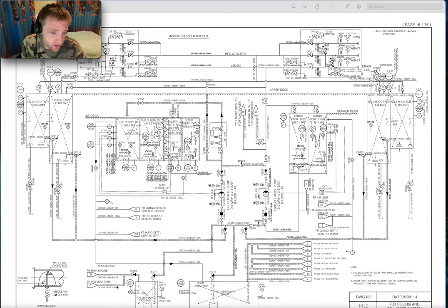So from this diesel generator, most of the leakage that you had previously in the Himsen engines was from the filters itself. There was a button, so when you turn the filters, you press this button and all the dirt was blown down to the tank. But after a short period, this kind of blowdown system from the filter was clogged and remained in open or in semi-open position, and from there you were losing fuel, because if you touch the line below, you will see that it's hot. Normally it must be a normal temperature, engine room temperature.